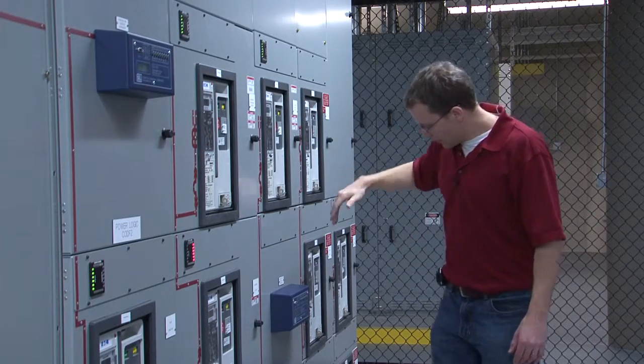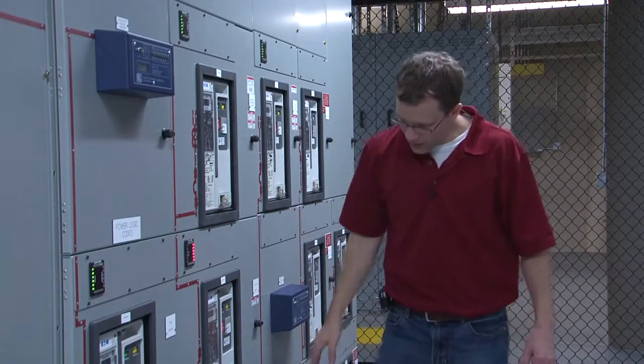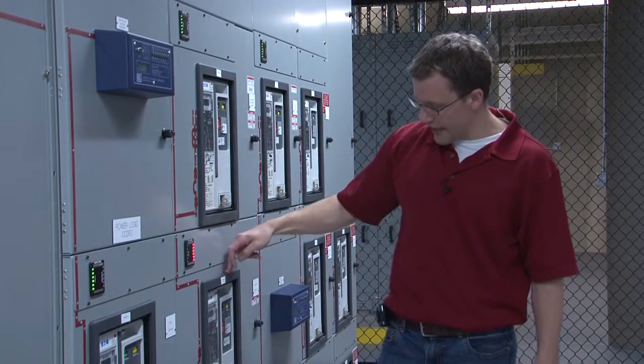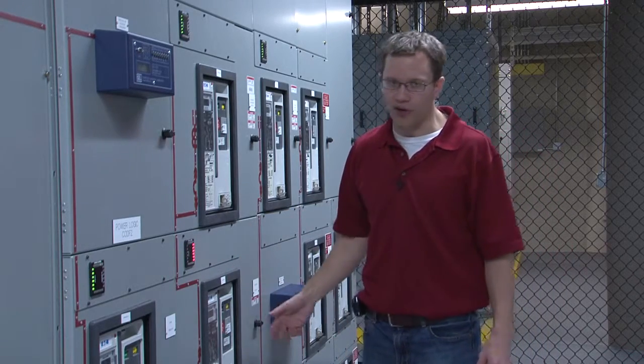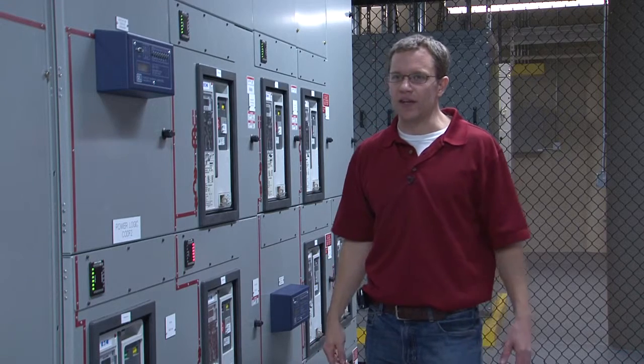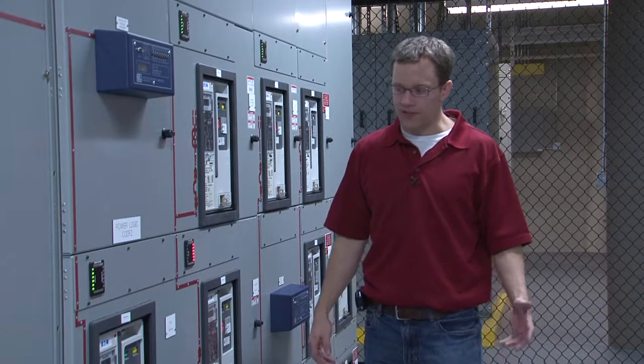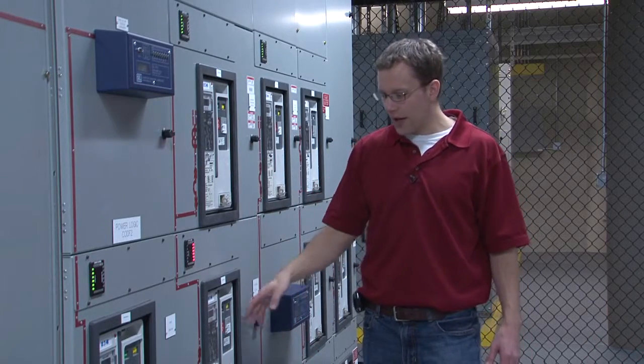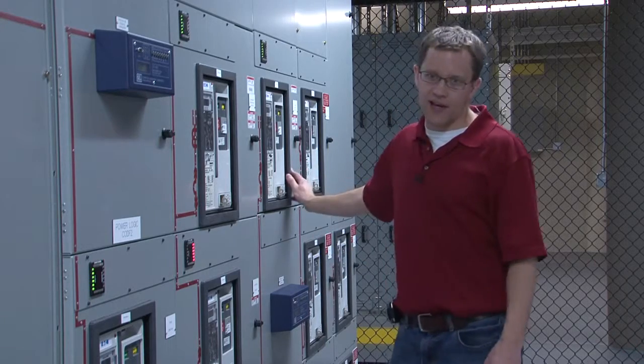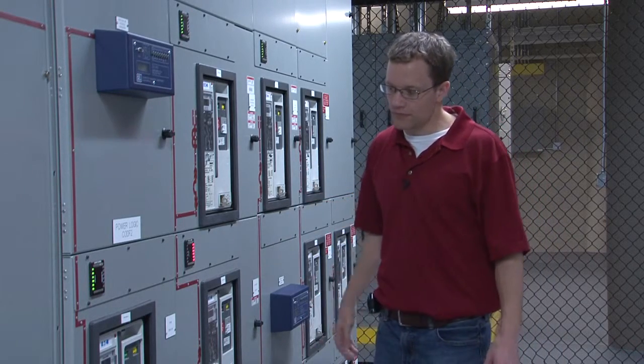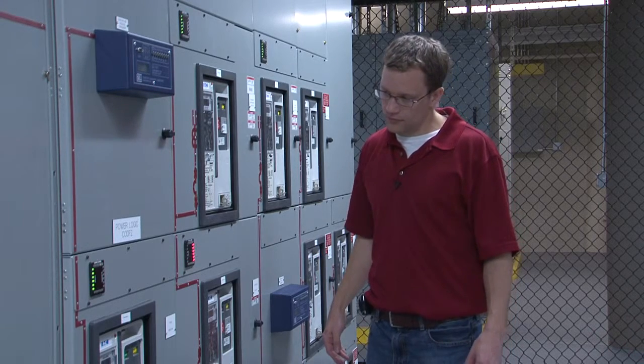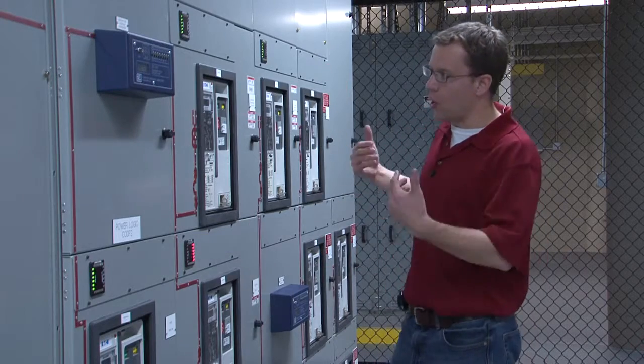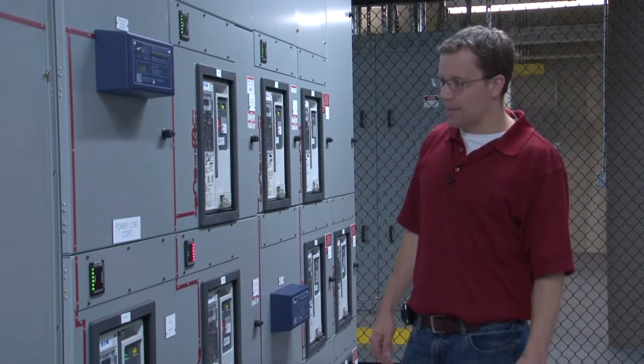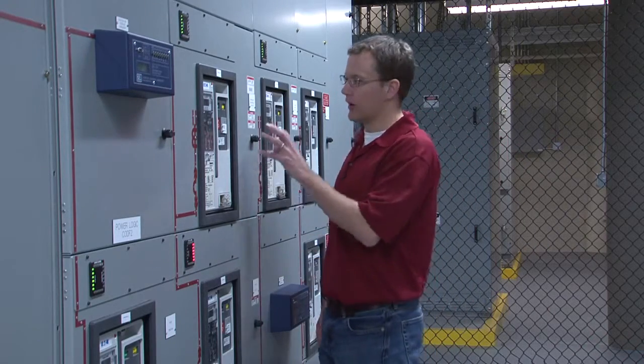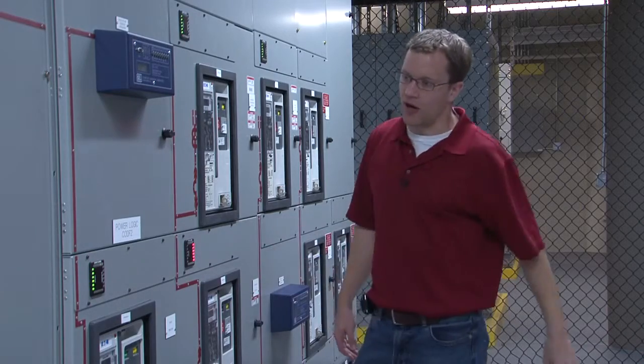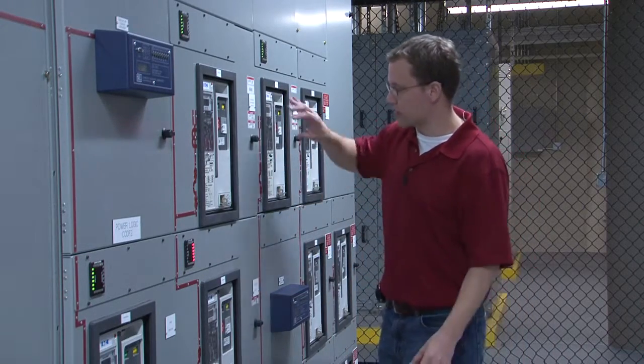So after power flows into this board from each UPS module, it comes down, it comes over, and it comes up through the isolation breaker, called the ISO breaker. And this breaker is meant to isolate the UPSs during maintenance. So during a maintenance condition, this breaker would be open, this breaker would be closed, and your UPS system would be isolated, and then you could do your load bank test or shut the UPSs down without affecting anything. As with the other breakers, these are all breakers that can be racked out. There is ground fault on this breaker, this breaker, this breaker, and that breaker. Unlike the ones here, it has not been defeated in these other locations.